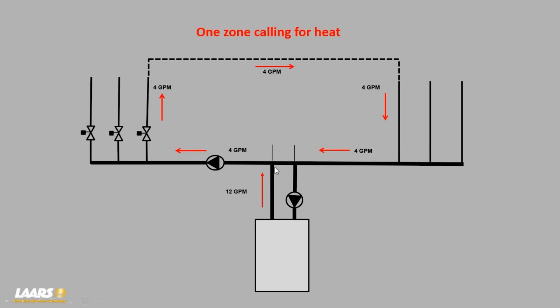Well, if I put 12 GPM into a T and I've only got 4 GPM going out to the zone, where's my other 8 GPM? It travels backwards through the 2 closely spaced T's because there's no pressure drop or minimal pressure drop here. And that meets up with the returning 4 GPM, and it guarantees the boiler its proper flow rate. That's why most manufacturers prefer primary, secondary, or hydraulic separation.